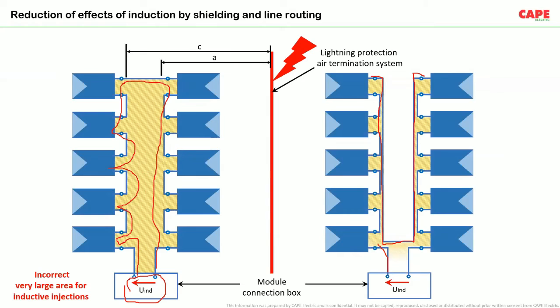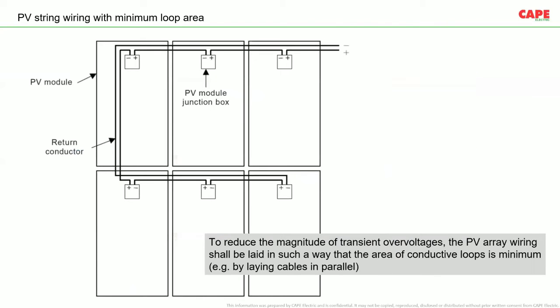Whereas in the second case, the loop is reduced to a very low level. As a result, the induced voltage is very much less. So basically, for the wiring which you are doing on the DC side, you should ensure that the positive and negative wires are routed in such a way that the loop is reduced to a very low level. And here you can see this recommendation in the standard.